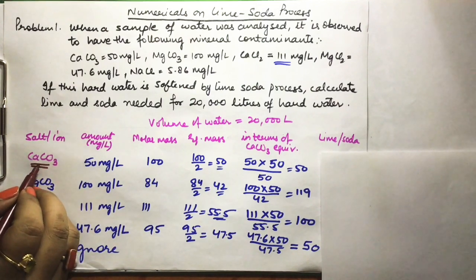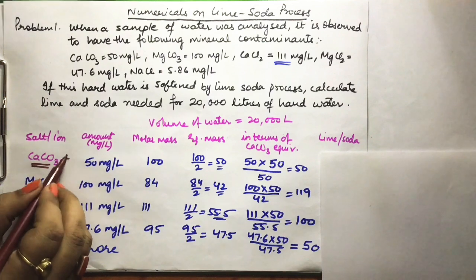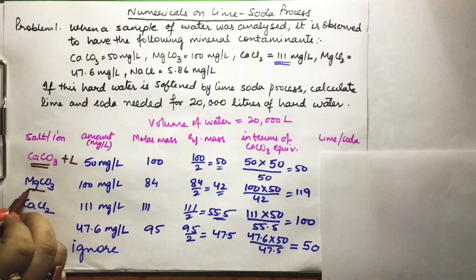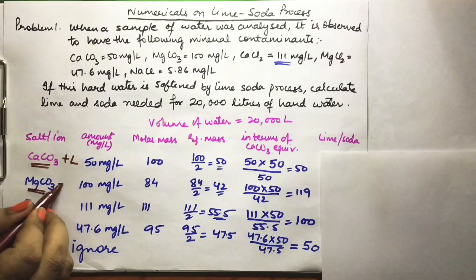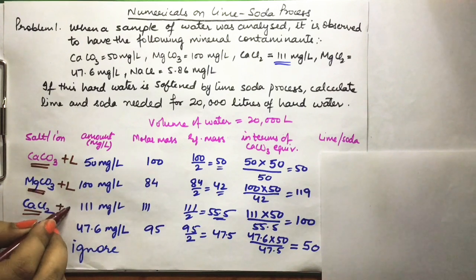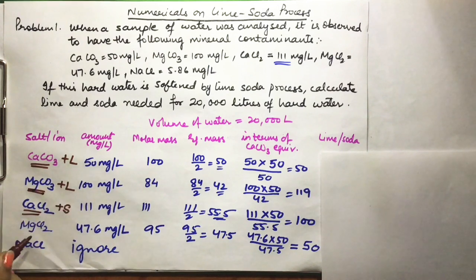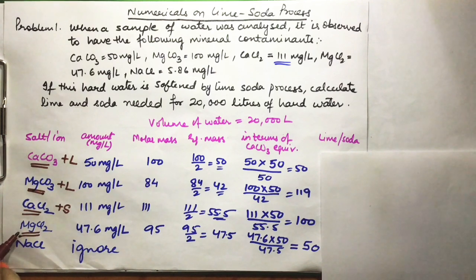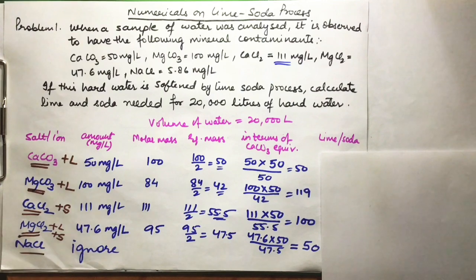Now we identify which salts go into lime and which go into soda. CaCO3 is temporary hardness of calcium — goes to lime. MgCO3 is temporary hardness of magnesium — goes to lime. CaCl2 is permanent hardness of calcium — goes to soda. MgCl2 is permanent hardness of magnesium — goes to both lime and soda. NaCl is ignored.